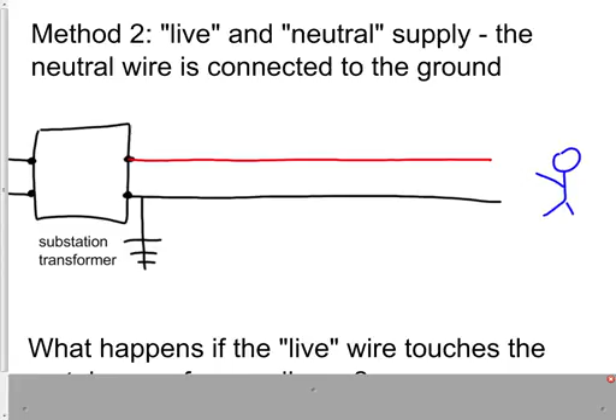Which can hopefully be detected by a circuit breaker tripping. So wires coming into contact with the earth will either trip a circuit breaker or not be an issue. Now what happens if the live wire touches the metal case of an appliance? Let's get our appliance again, just a box for ease of drawing. Inside it, the wire is connected to a heating element with a switch and fuse in the plug, everything's working fine, but somehow a bit of live wire manages to touch the metal case. The situation here is if you touch the metal case when the live wire is in contact with it, current can flow through you, through the ground, back to the substation, and you get an electric shock, which is bad.